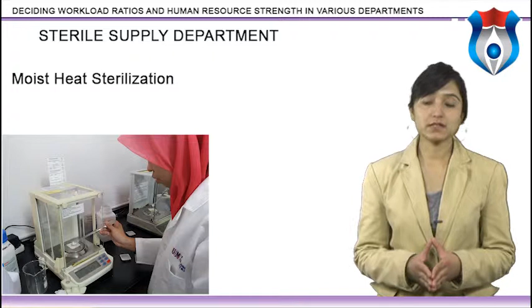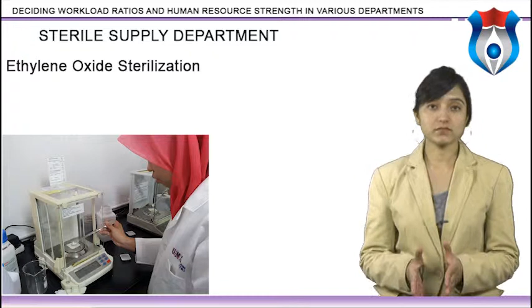Ethylene oxide sterilization. Ethylene oxide sterilization is used for thermolabile reusable medical supplies made of plastic. The sterilization medium is a mixture of ethylene oxide and vapor that penetrates well. This moist sterilization process requires a period of post-sterilization aeration to remove toxic residues.